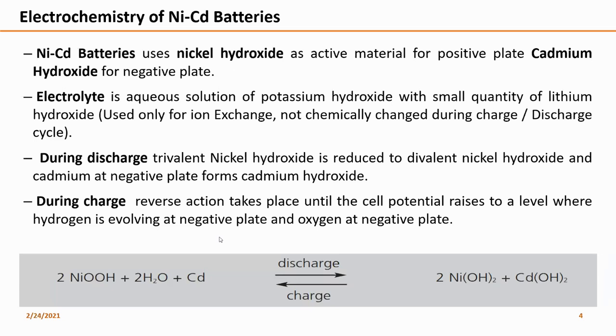For example, with lead acid batteries, every month or quarter depending on operation, we used to top up the electrolyte regularly. There are sealed lead acid batteries that don't need this, but in industry we mostly don't use the sealed type. So for nickel cadmium, the chemistry is clear that there's no need for regular electrolyte updation.